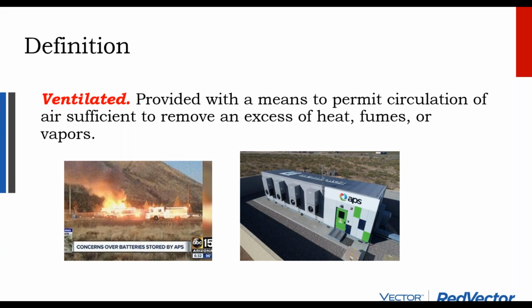The question becomes, does a sealed battery also need to be ventilated? You could say that's a great advantage of having a sealed battery, that you don't need ventilation. But the problem becomes, what happens when a sealed battery becomes unsealed, and let's say, for discussion purposes, through no fault of the battery itself. Let's say the building's on fire and the fire makes it to the battery room and starts burning up the casing of the batteries, and it heats the battery to the point where it catches on fire. In that case, what was a sealed battery becomes an unsealed battery.